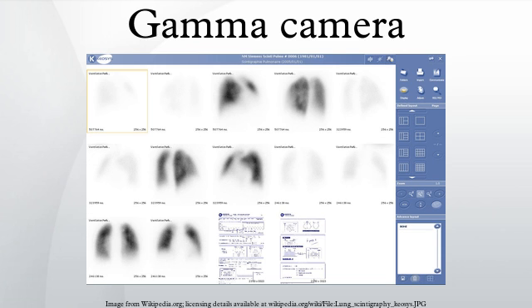The total sum of the voltages from each photomultiplier is proportional to the energy of the gamma ray interaction, thus allowing discrimination between different isotopes or between scattered and direct photons.